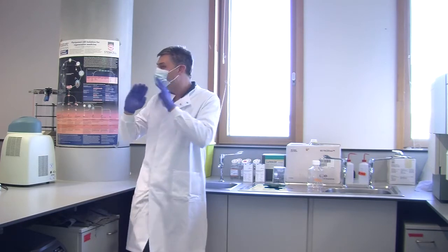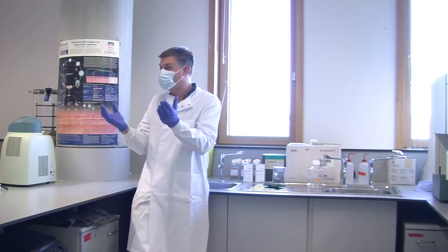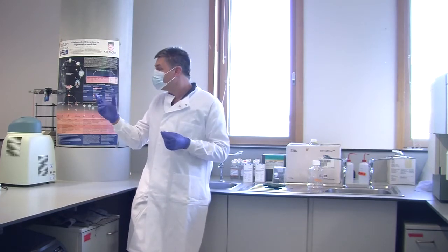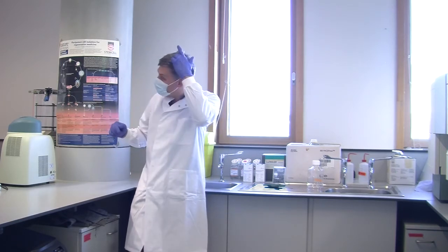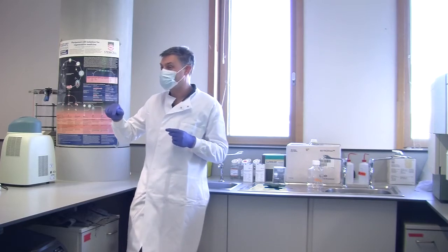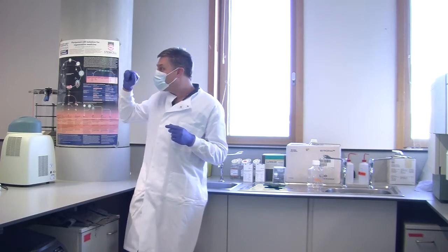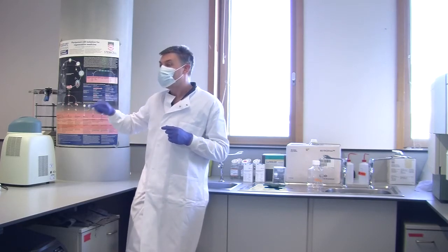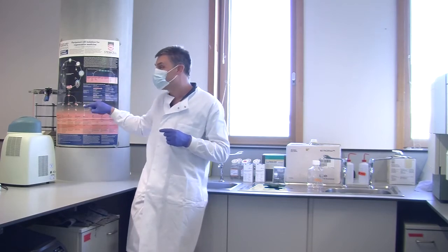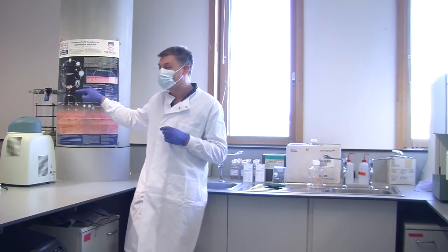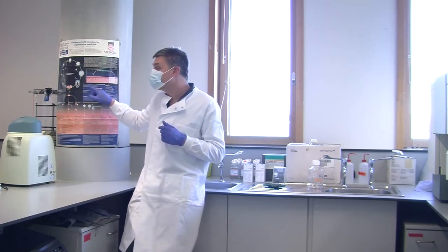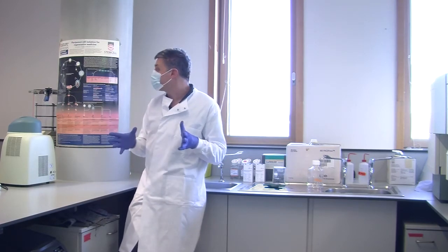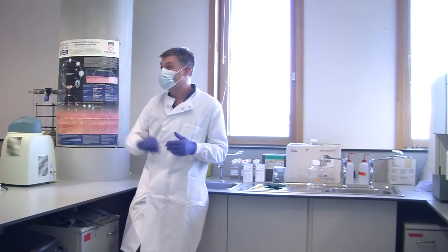Now these centrifuges are lined with titanium walls. And the centrifuge bucket punched a hole in the titanium, punched a hole in the breeze block wall of the centrifuge room, punched a hole in the wall of the other side of the corridor, travelled across the office, punched a hole in the breeze block wall of the office onto the outside, and disappeared off into the outside. And I think it was only found about 6 months later because it just went, half a mile or whatever it was.